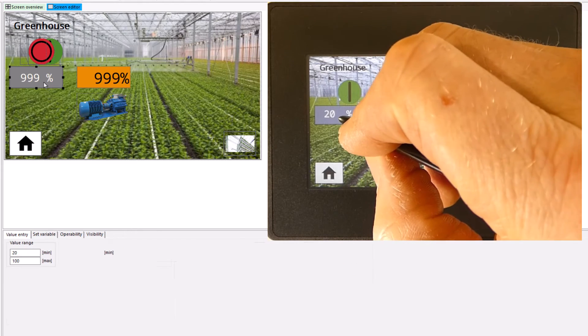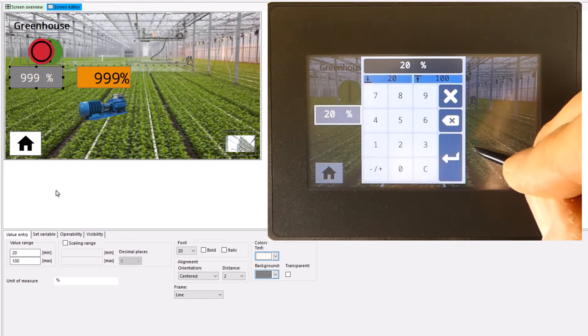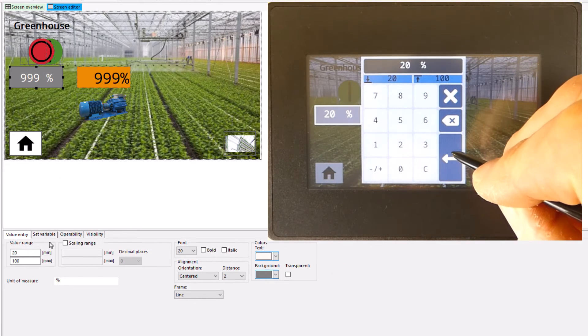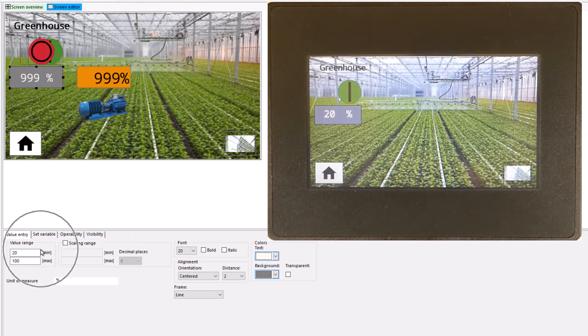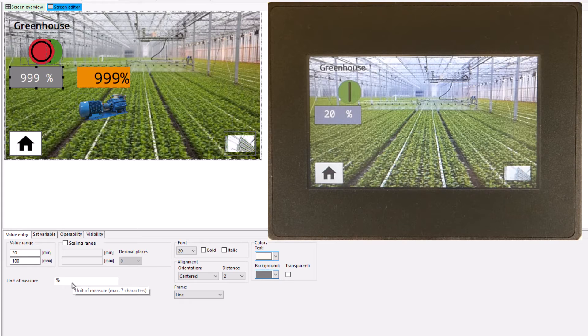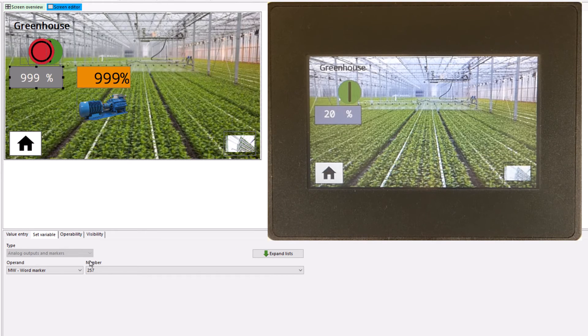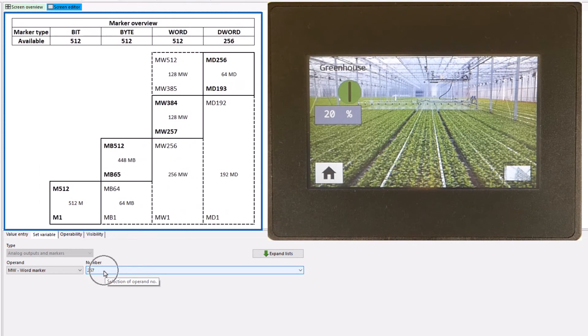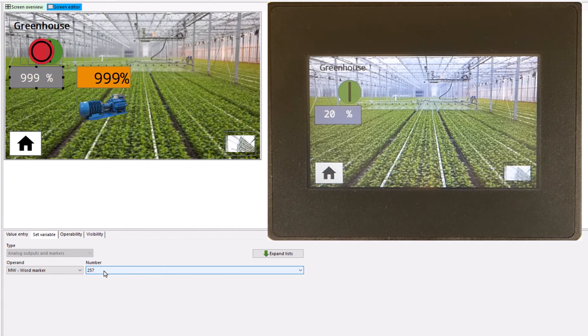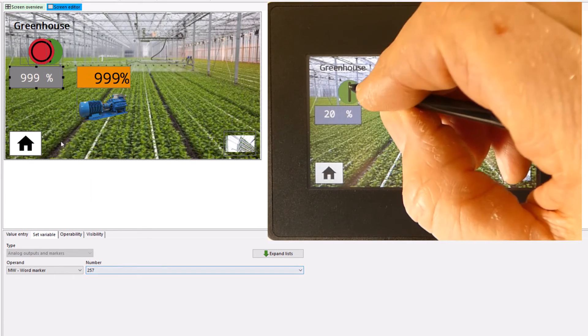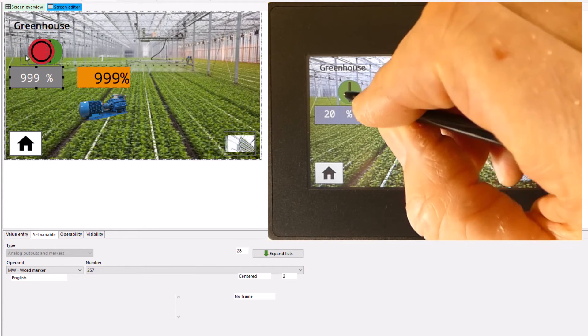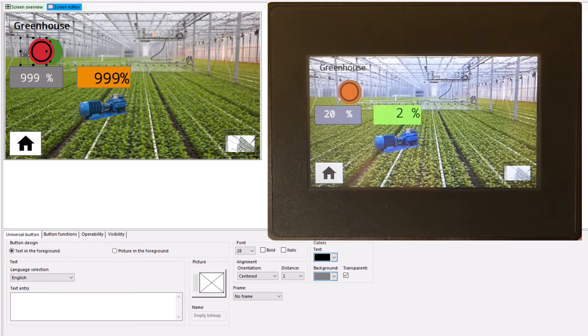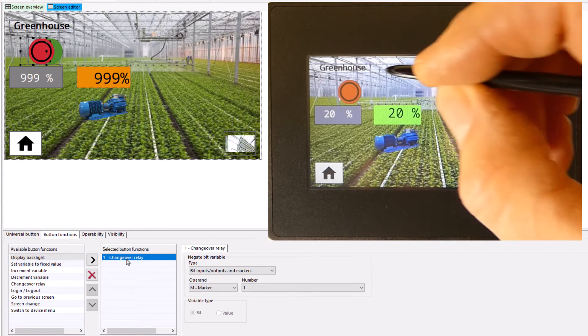The value entry input element was positioned on the left for the setpoint specification. The value range was configured to 20 to 100 with the unit of measure percentage and assigned to the marker word 257. This value was selected to avoid unwanted overlaps with marker bits or marker bytes. A transparent universal button with the changeover relay button function was created as the on-off button.